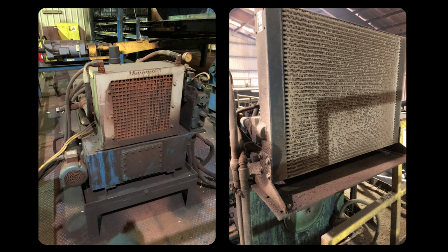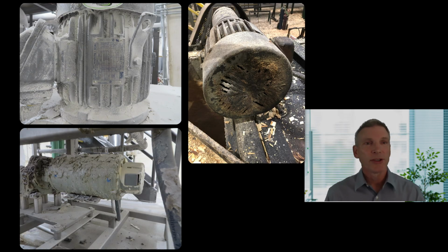I think also over time that you break down the hydraulic oil faster if your temperature is very high. Motors is another one that's usually fouled, and you can see dust and product on top of them. And you see the inlet for the fan there is actually clogged up. That motor is overheating, and a lot of times, we'll see the winding insulation going bad and shorting the motor out, or we overheat the bearings, spit out the grease, and then we have to change the bearings.